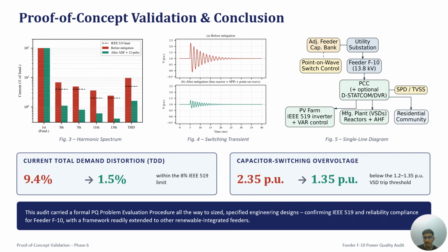So to conclude, this audit carried a formal PQ problem evaluation procedure all the way from raw monitoring data through sized, specified engineering designs, and this confirms both IEEE 519 and reliability compliance for feeder F10, with a framework that is readily extended to the other renewable integrated feeders.